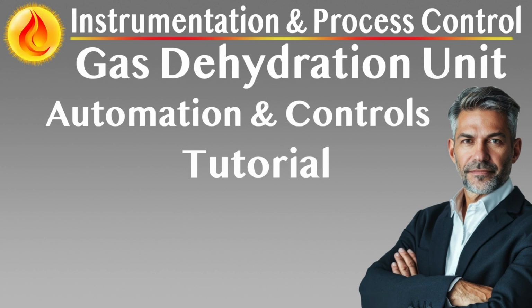All controls are seamlessly integrated with the overall dehydration unit automation platform, typically via the Distributed Control System, DCS, or a local control panel, and are governed by project-defined safety integrity levels, SILs. Instrumentation on the contactor is designed to control key process variables such as pressure, temperature, gas and glycol flows, level interface management, and gas glycol contacting efficiency, while enabling fail-safe shutdowns under abnormal conditions.